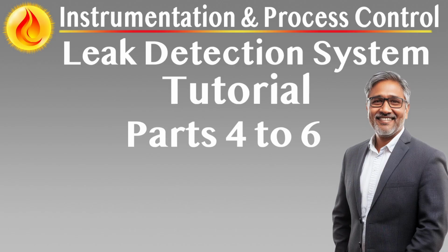Alarm management must be carefully configured. Leak alarms generated by the LDS are advisory in nature and should not directly trigger automated shutdowns unless validated through secondary systems like smart LBVs. Manual operator intervention remains the standard response, ensuring that human oversight governs critical decisions. Alarm thresholds, filtering logic, and display integration must be designed to minimize nuisance events while preserving timely and actionable alerts.